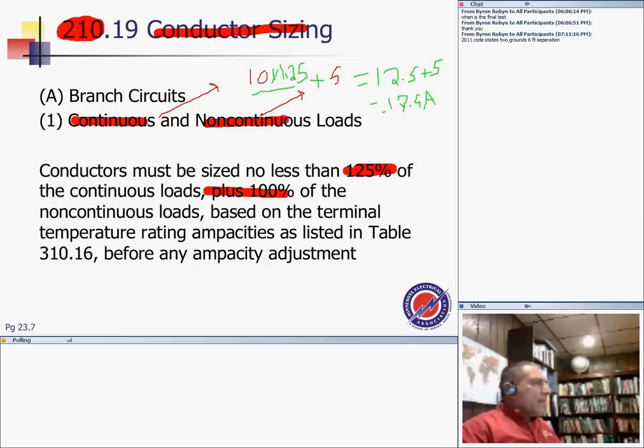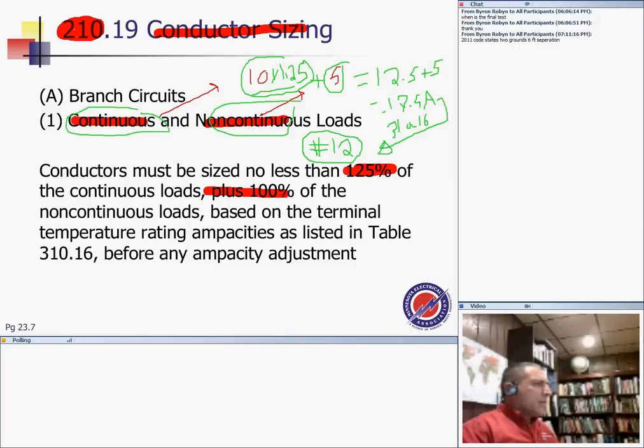You go to table 310.16, and you size it for a number 12 conductor. So I have a number 12 conductor, and I size it based on the continuous load at 125%, which is right in here, and the non-continuous load, which is only 100%. You go to table 310.16 and you size it. Any questions, guys, about sizing branch circuits based on continuous load and non-continuous load?